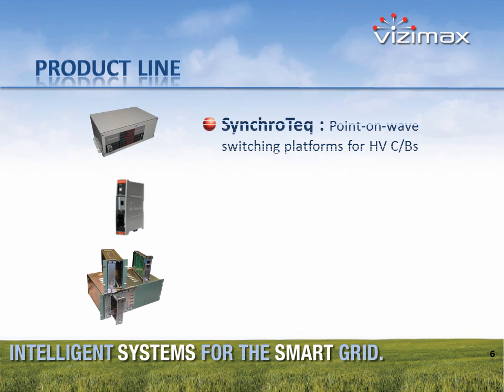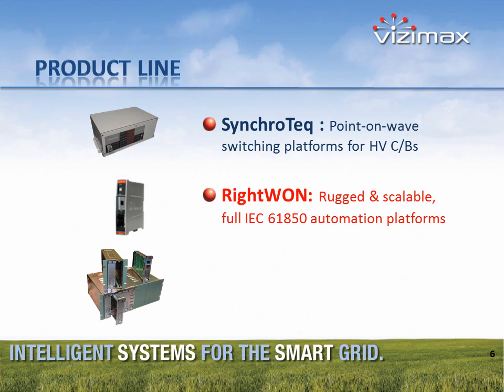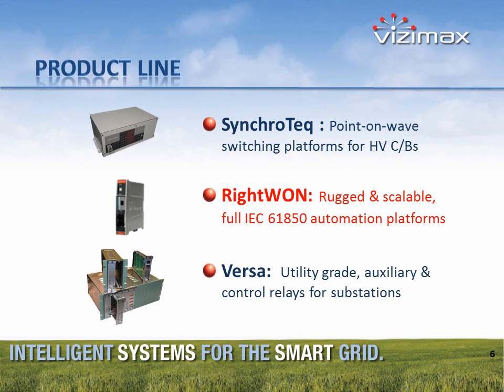Vizimax currently carries three product lines. The first is the SynchroTeq product line, a family of point-on-wave switching platforms for high-voltage circuit breakers. This device allows circuit breakers to be operated at very precise moments to avoid transients on high-voltage networks. The second is the RightWON product line, a rugged, scalable, full IEC 61850 automation platform. Finally, the third product line is Versa, utility-grade auxiliary and control relays for substations, which also includes high-power interfaces to circuit breakers.